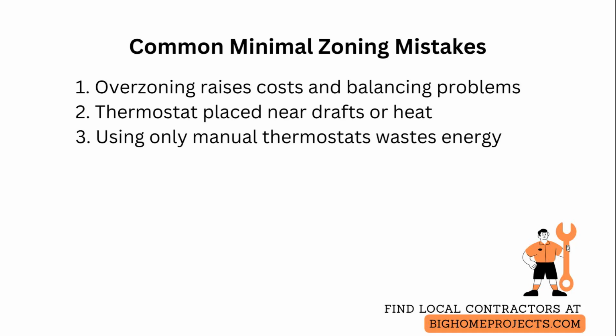Another issue is poor thermostat placement next to drafts or heat sources, which leads to misregulated cycles. Place thermostats on interior walls about 5 feet off the floor away from direct sun and registers.